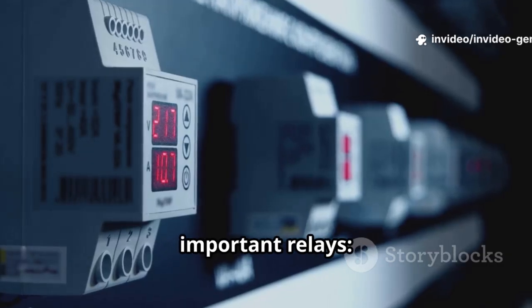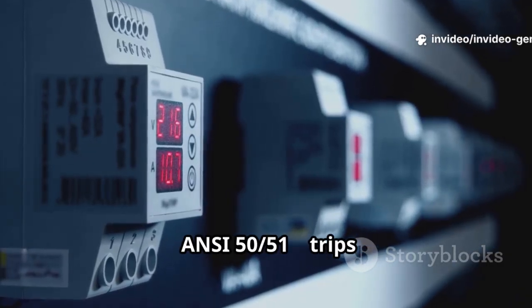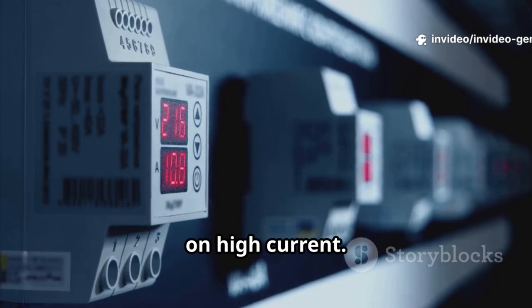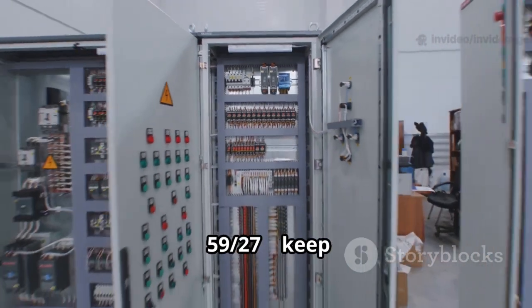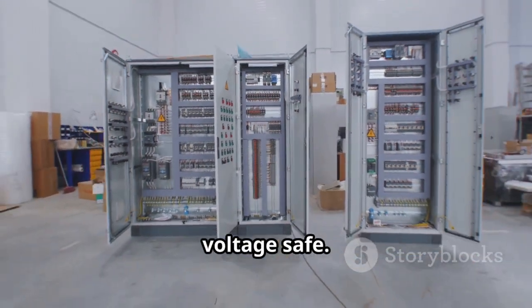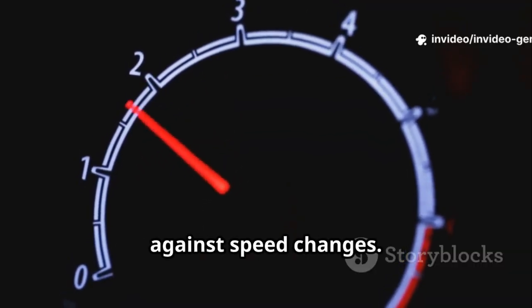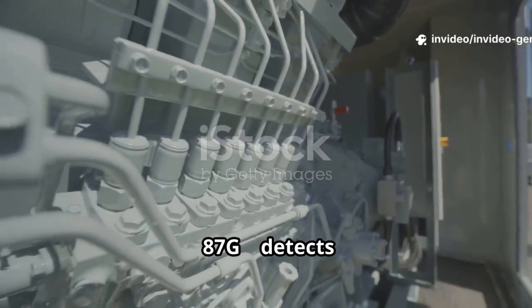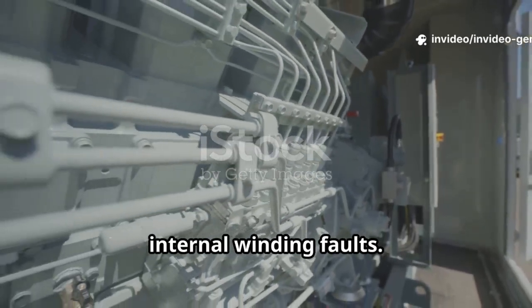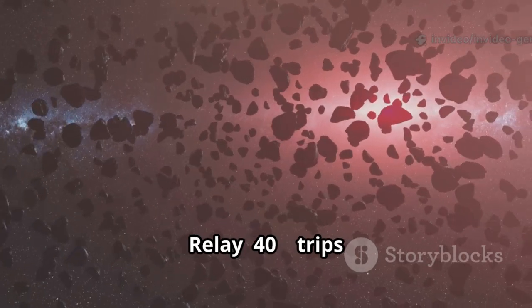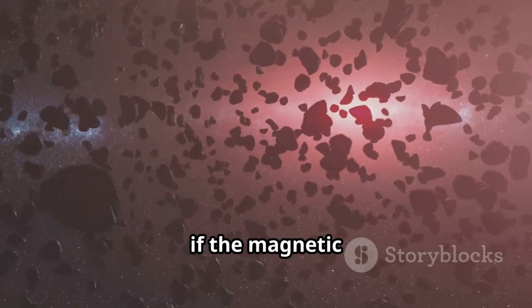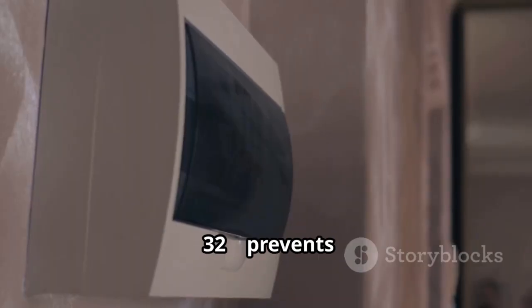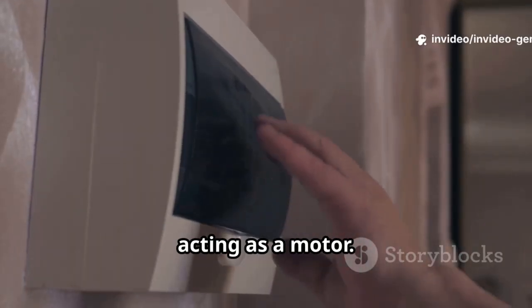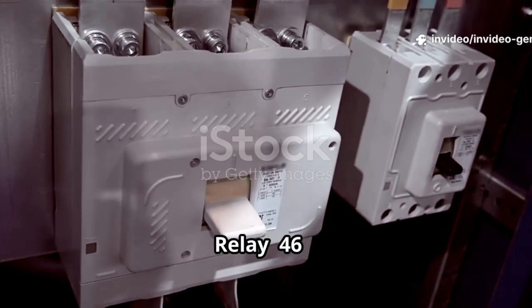Here are the most important relays. Overcurrent relay, ANSI 50/51, trips on high current. Overvoltage and undervoltage relays, 59/27, keep voltage safe. Frequency relays, 81O/81U, protect against speed changes. Differential relay, 87G, detects internal winding faults. Loss of excitation relay, 40, trips if the magnetic field is lost. Reverse power relay, 32, prevents the generator from acting as a motor. Negative sequence relay, 46, protects against unbalanced load currents.